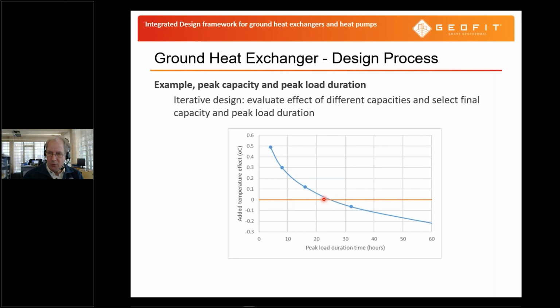On the other hand, if we already have a longer peak load in the design and the peak load time increases, the effect on the temperature is very small in this area, for instance. So this is just a trade-off between a longer heat exchanger and more robustness with regard to peak load duration, and a shorter heat exchanger that can handle a shorter peak load but not a much longer one. So it depends on the system design whether that is an intelligent choice or not.